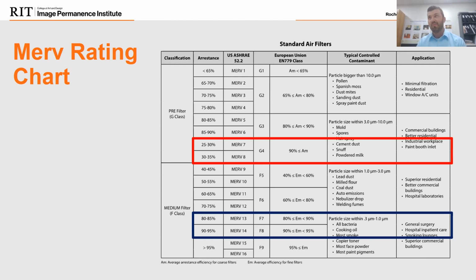I'm not sure how much was learned. I know we did our own study. A lot of the problems with moving up to a MERV 14 filter, which is one of the things I wanted to cover, is if your air handling unit was not designed to handle a MERV 14 filter, if it was only ever designed for, say, a MERV 8, you can't install the MERV 14 because it would impede the airflow. So a number of collecting institutions couldn't install the MERV 13, 14 filters. They wound up having to install alternate methods, things like UV lighting inside the ductwork, or ionizers inside the ductwork as well.